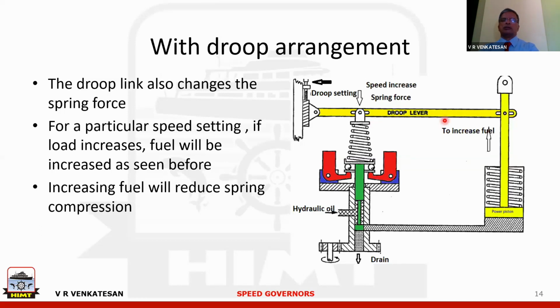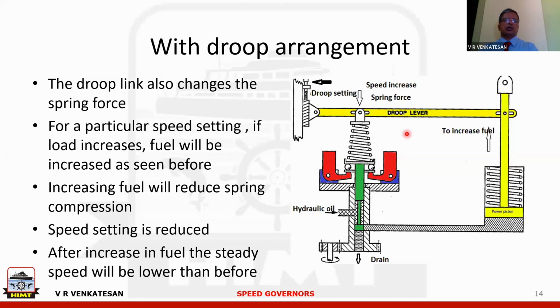This is a schematic drawing. Actual construction is a little more complicated, but this explains the principle. How much the droop setting will be is changed here. So if you make the droop setting 0, then the movement of this lever will not make any difference to the spring. This is how droop is given. So because of this droop, even though the fuel is increased and the engine is handling more kilowatt, the steady speed will be a little bit less.